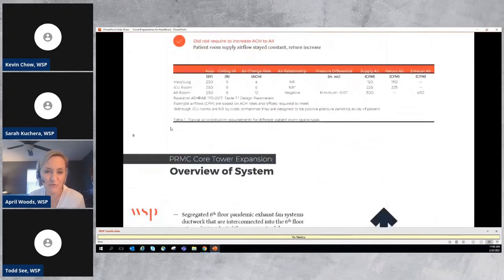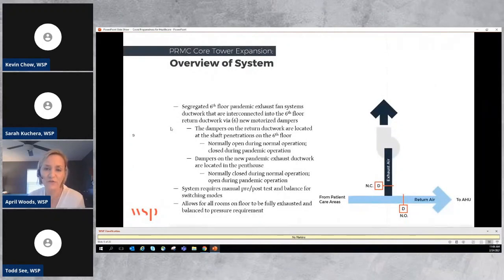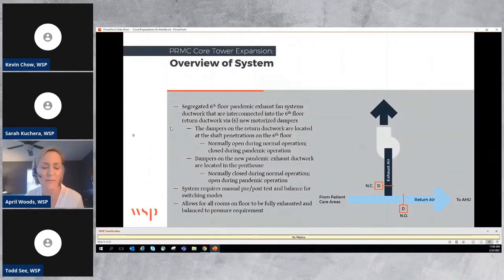So on the next slide, it kind of shows you a little bit about how the strategy works here. So rather than returning the air back to the air handling unit, we were able to segregate the airstream into a pandemic exhaust system. This was really strategic, just based off of how flexible we had designed the air systems, with 2 air handling units in the penthouse that distributed all the way down the tower, separated by the smoke compartments. It allowed for each individual smoke compartment to be operated individually, but it allowed for all of that air, rather than returning back to the air unit, to be fully exhausted.